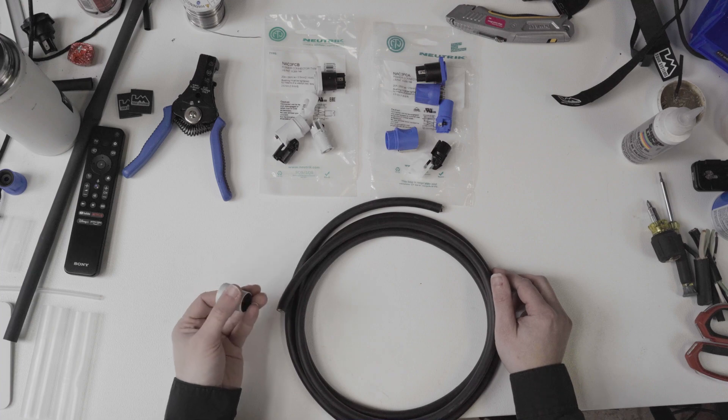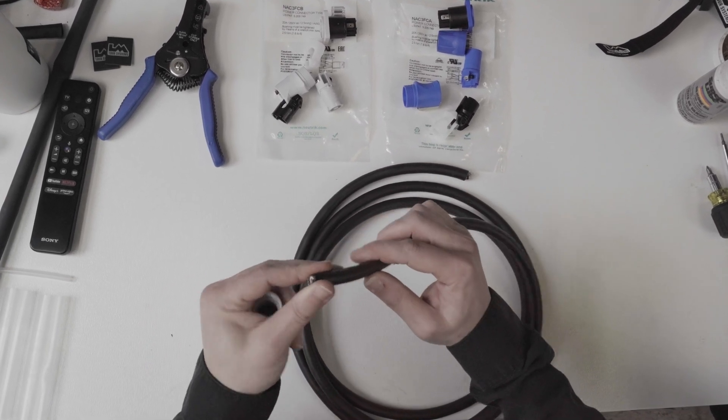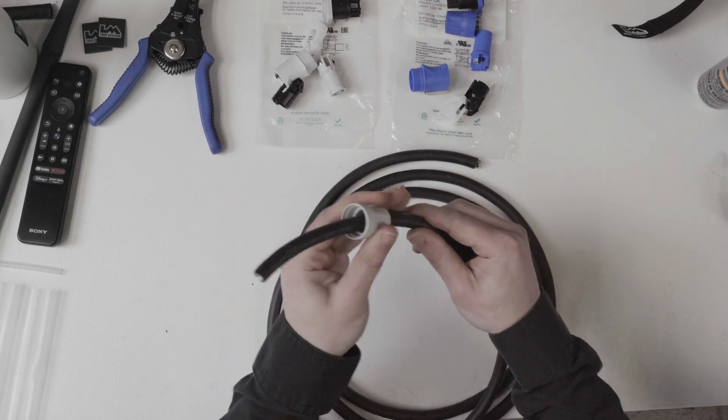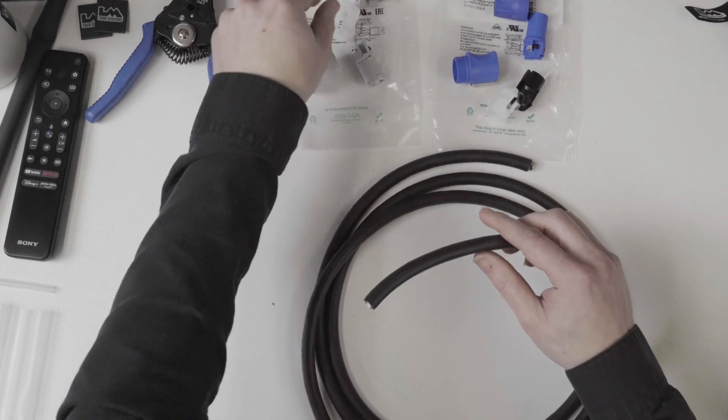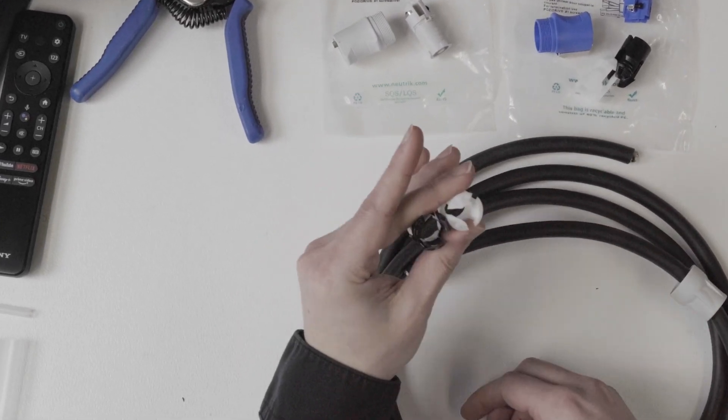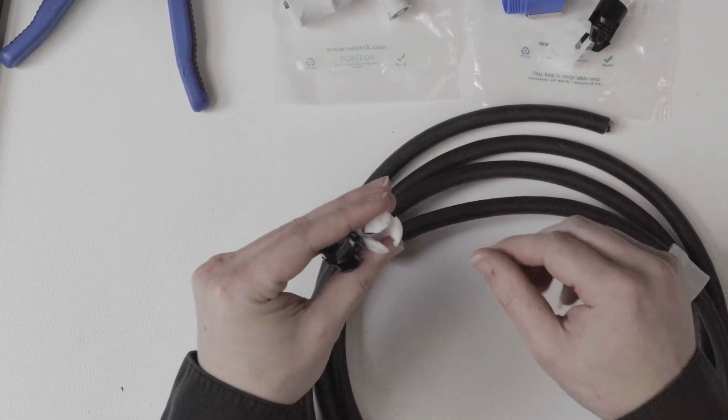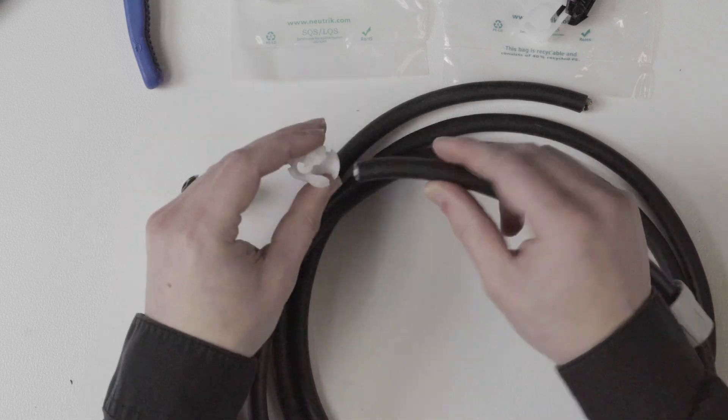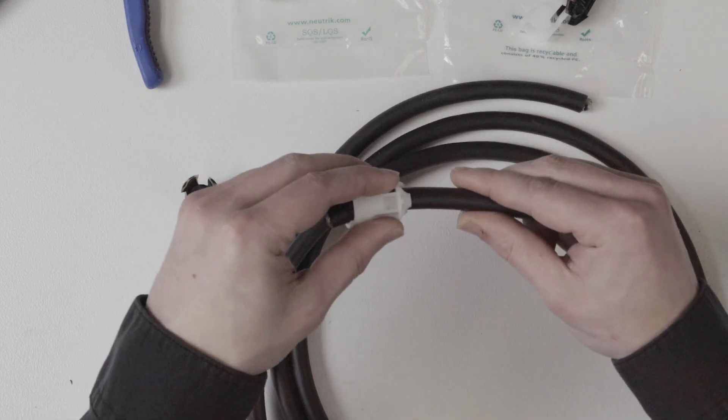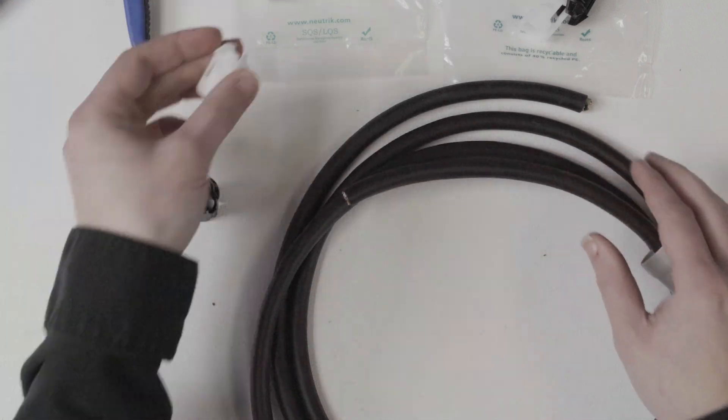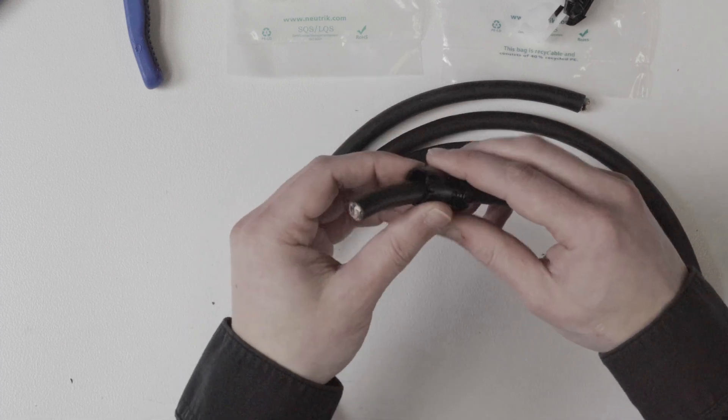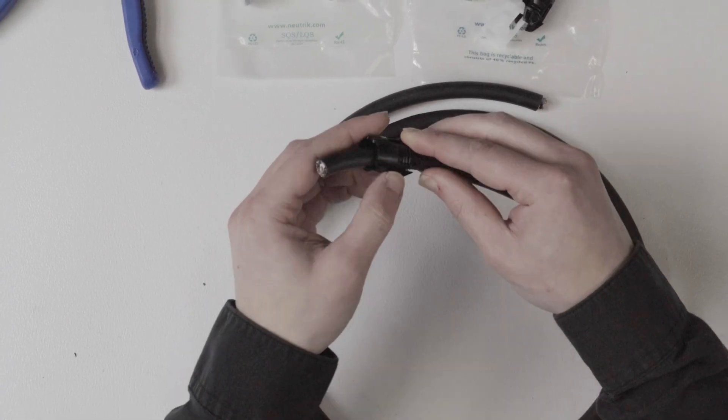So we're going to start with the NAC3 FCB. This is the output side. So we'll just slide our back boot on first. So each of these connectors have two different cable glands here on the back. There's a black one and a white one. The black one works well for 12 gauge which is what this is. This is 12 gauge SO. The white one is for thinner cable. Now you can smash the white one on here but you don't need to. So we're gonna slide this guy on. Now these do have a little cut in there so that if you forget about it you can kind of get it on there but on the thicker cables it's a little bit of a problem.